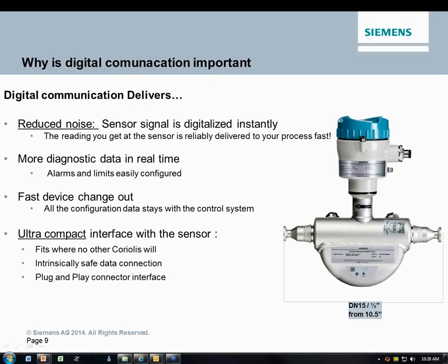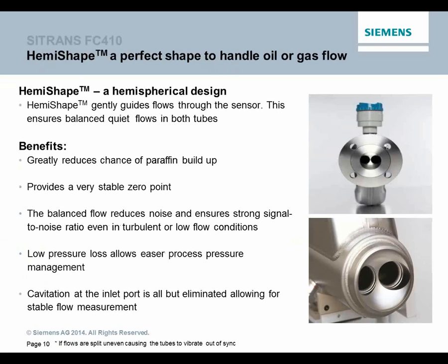What I was talking about when I started this slide was the digital stuff, and I'm going to go quickly now because I can see our time is almost up. The design and the consideration for digital communication was done to reduce noise, to allow for a faster data update rate, to make it very quick and easy for a device change-out, process connections, one-wire connector. And of course, since it's so small, this sensor could fit more units, where some of the competition cannot quite squeeze in. Though some can, some are very good at it.